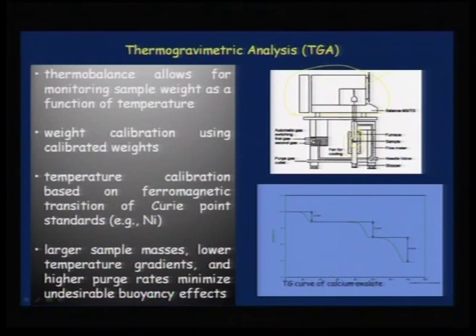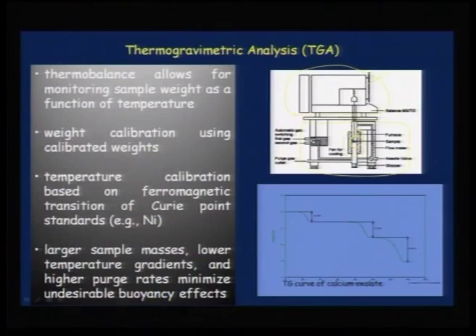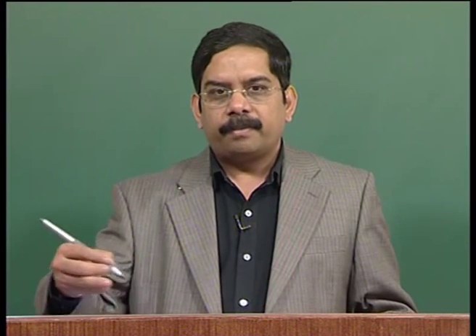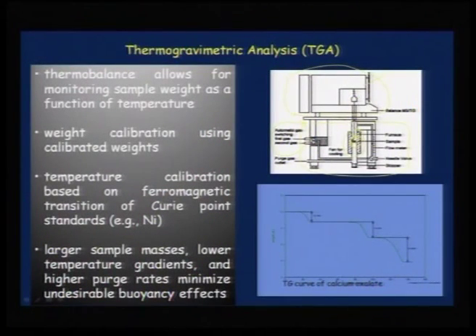The lower chamber can apply vacuum, and there are facilities to purge the sample with flow of either argon or air atmosphere. This ensures that if there is gas evolution, it is flushed out periodically. An inert gas is usually flushed, or if the sample needs air, we can flush with air and map the results.